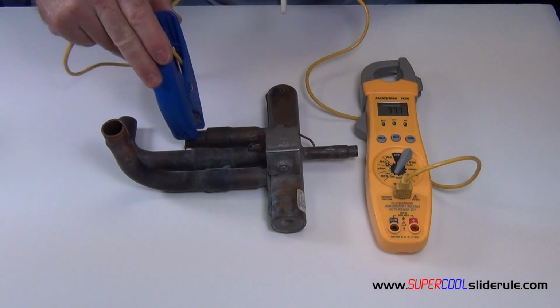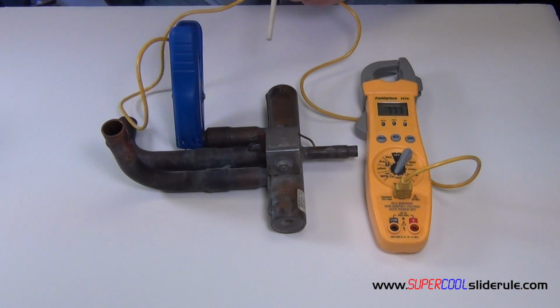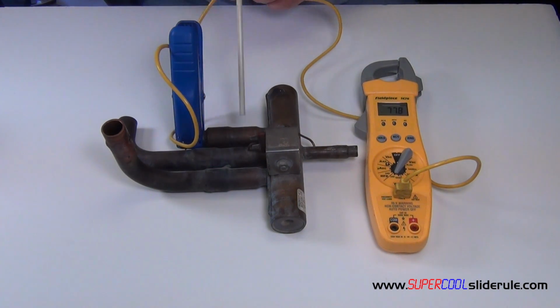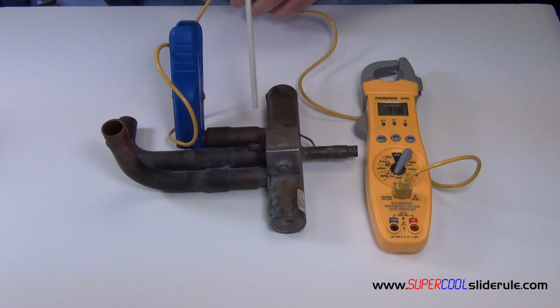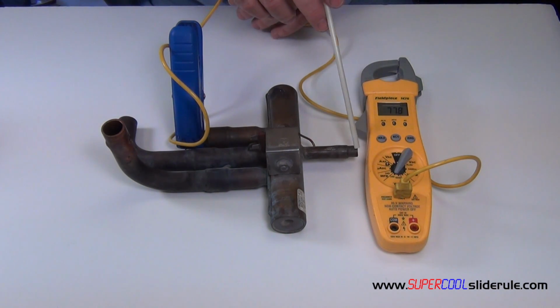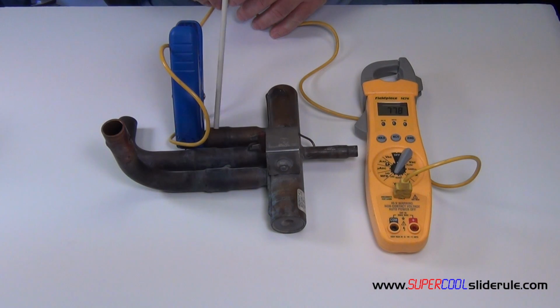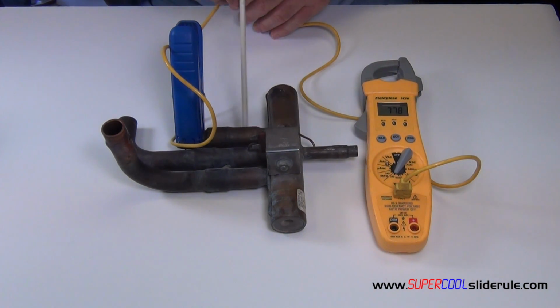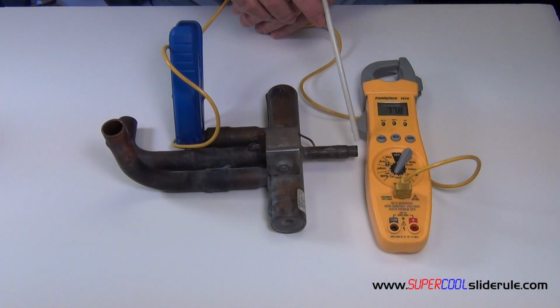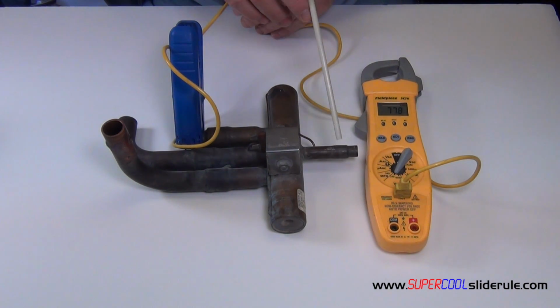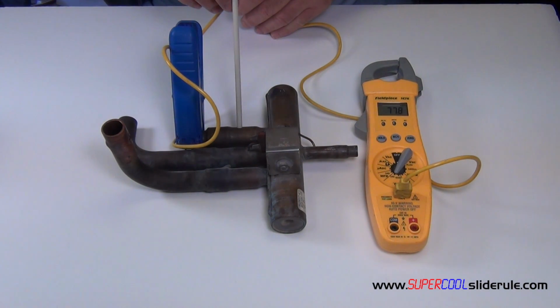Now, with the temperature clamp, if we get a reading, the reading that we receive on the lower tubes must be, let's say for instance right now we have hot gas here and hot gas on this circuit, we are looking for plus or minus 5 degrees of whatever this temperature is. So if this temperature, let's say, is for instance 200 degrees, this one must be 195 degrees or 205 degrees.